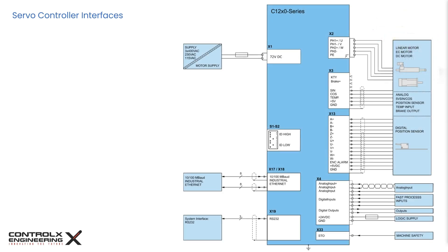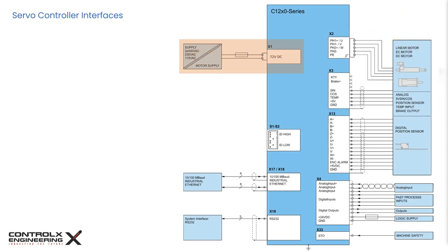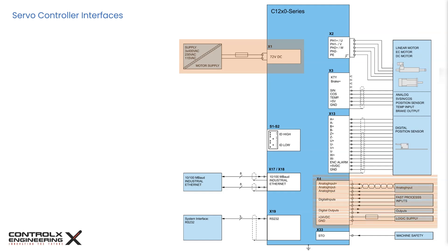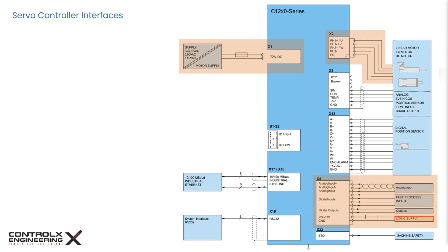This page from the user guide shows the typical servo drive connections. This model requires a 72V source for the motor supply on connector X1, as well as a 24V source for the drive electronics and logic controller on X4. The linear servo motor connects to X2.